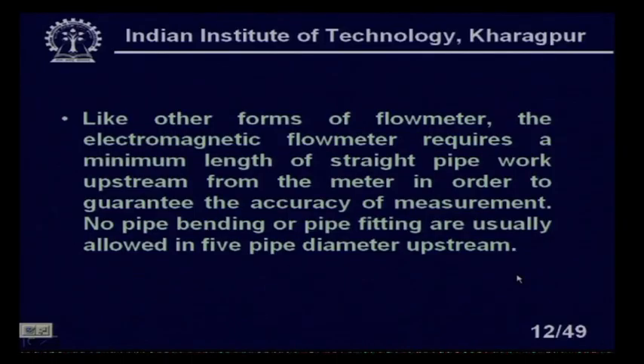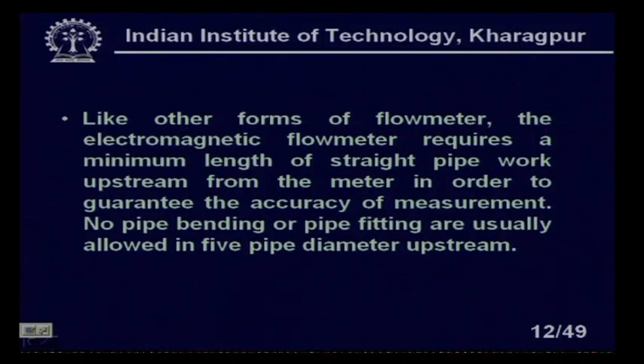Like other flow meters, the electromagnetic flow meter requires a minimum length of straight pipe work upstream to guarantee measurement accuracy. No pipe bending or pipe fittings are usually allowed in 5 pipe diameters upstream — this is less than the 20 pipe diameters required by some other flow meters. Note that this meter measures the average flow velocity.